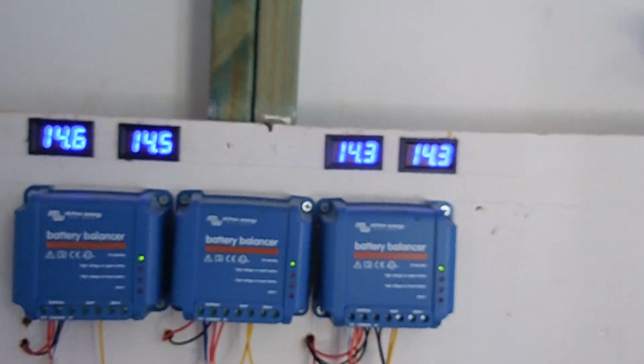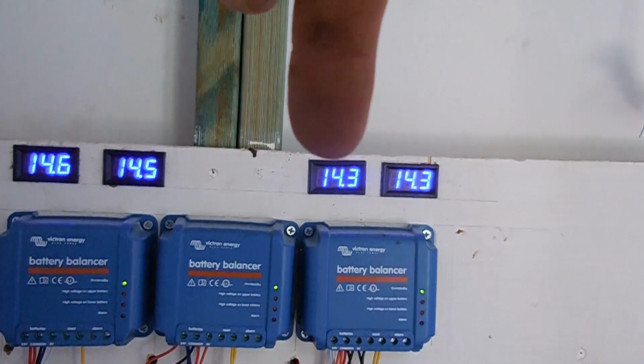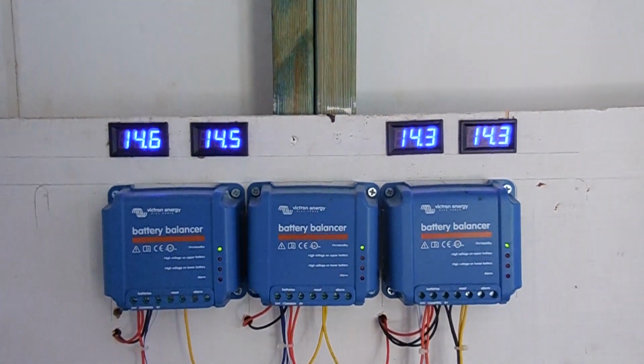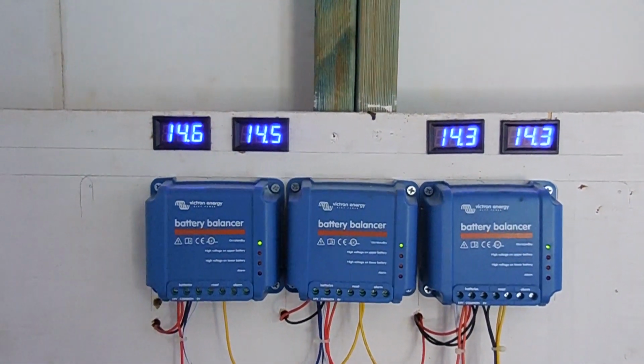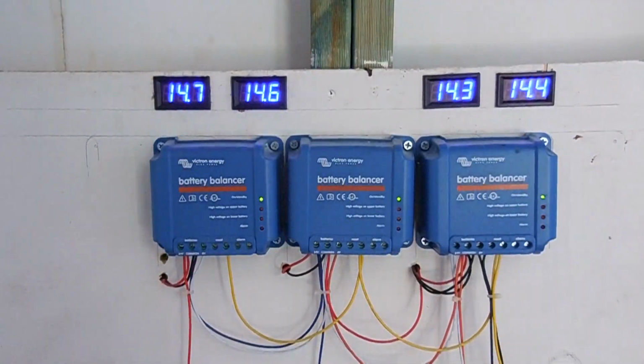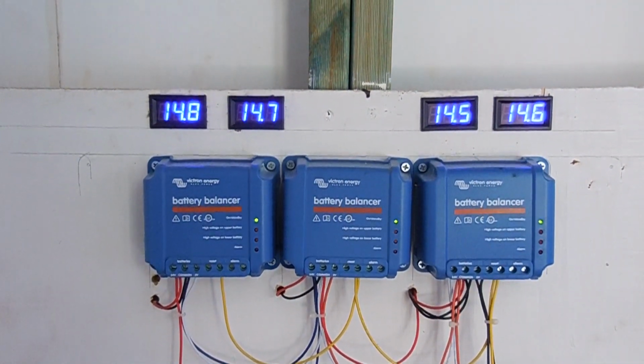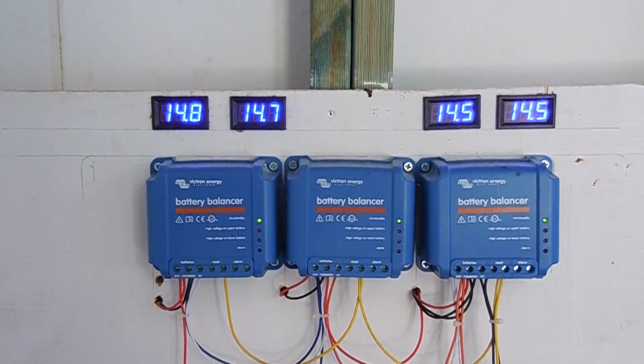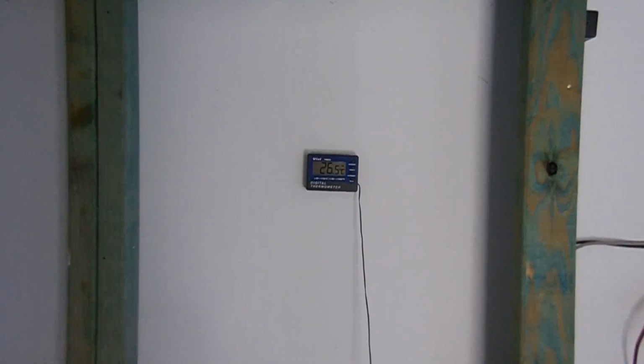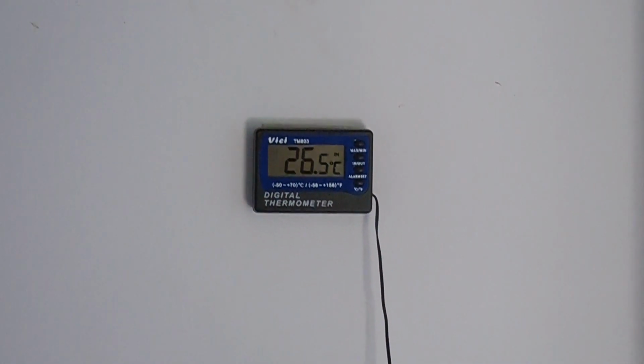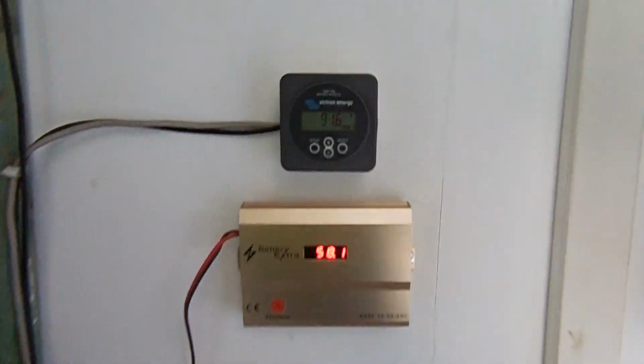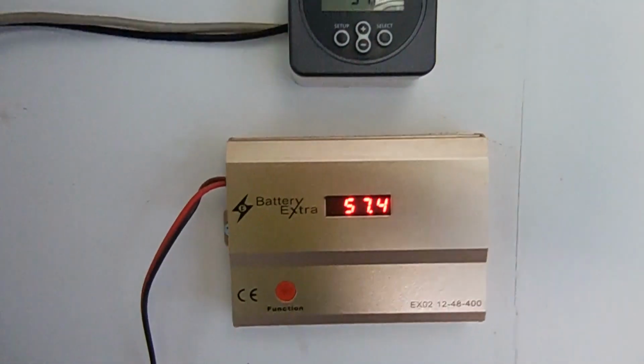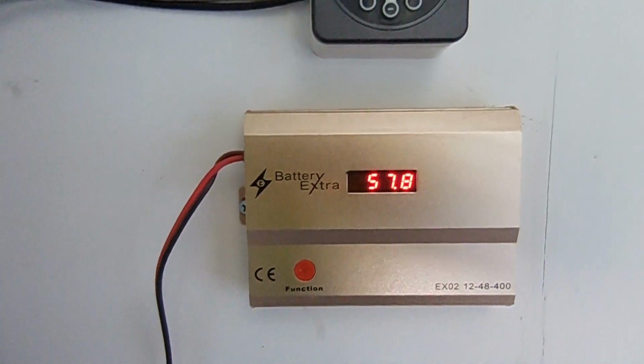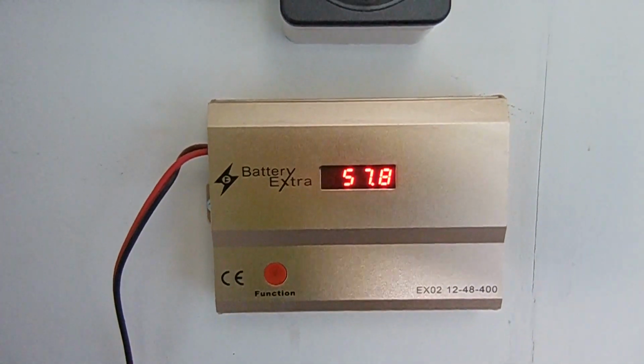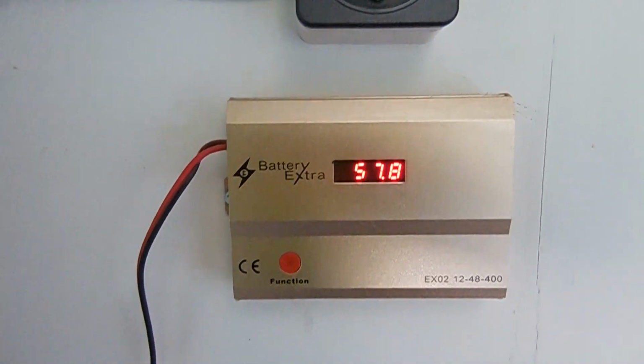The meter second from the right there actually reads slightly lower than it should. It's out of calibration, so I need to calibrate that or replace it if I can't calibrate it. So the battery balancers are doing their job at the moment. We have a temperature gauge in the power shed just to monitor the temperature in here. Also connected to the battery bank is this battery extra, which gives us our total voltage. So you can see we have 57.8 volts.